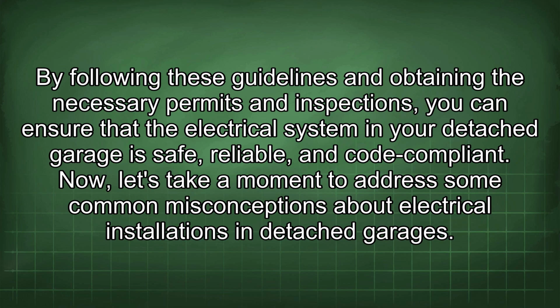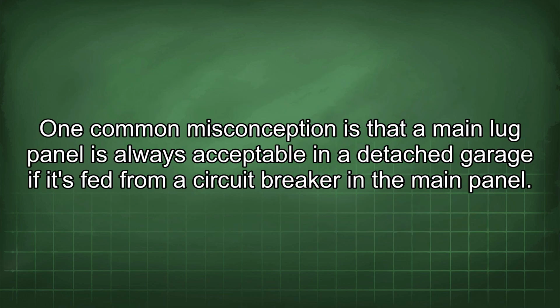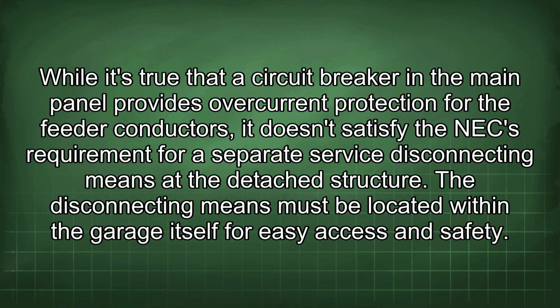Now let's take a moment to address some common misconceptions about electrical installations in detached garages. One common misconception is that a main lug panel is always acceptable in a detached garage if it's fed from a circuit breaker in the main panel. While it's true that a circuit breaker in the main panel provides overcurrent protection for the feeder conductors, it doesn't satisfy the NEC requirement for separate service disconnecting means at the detached structure. The disconnecting means must be located within the garage itself for easy access and safety.